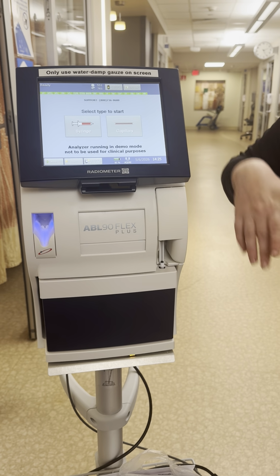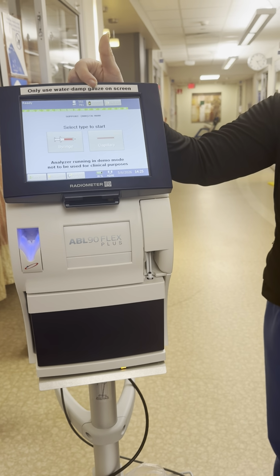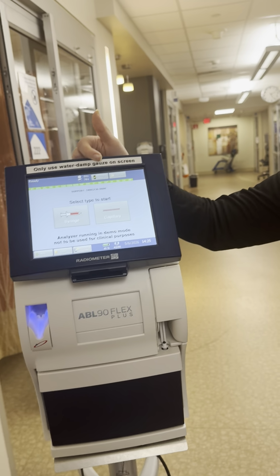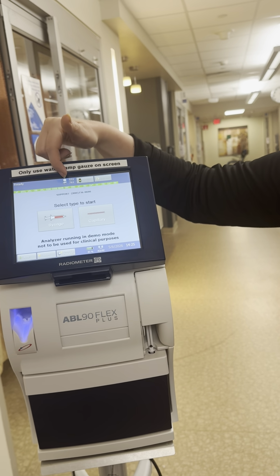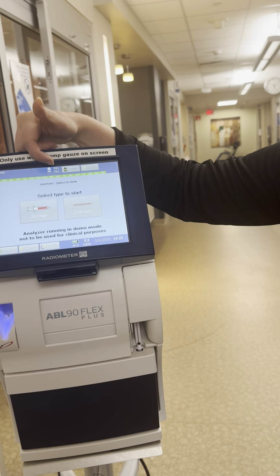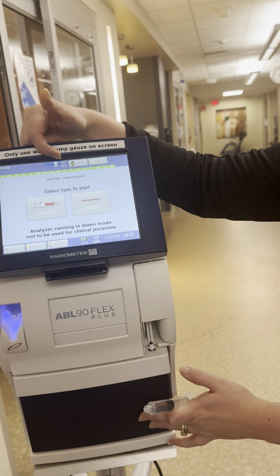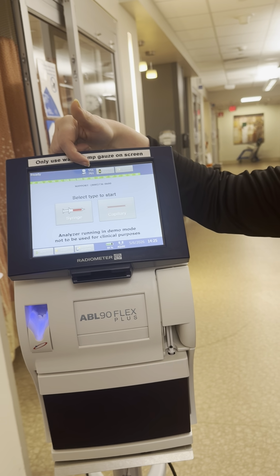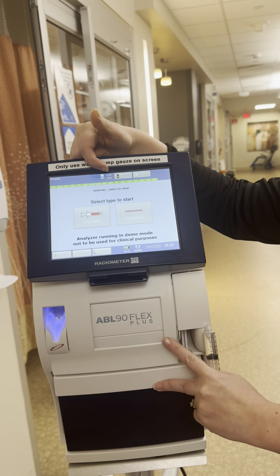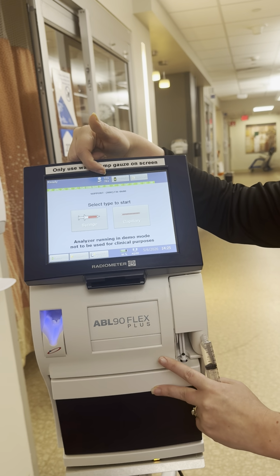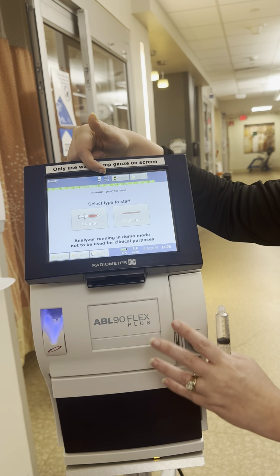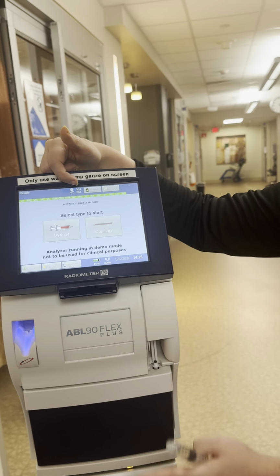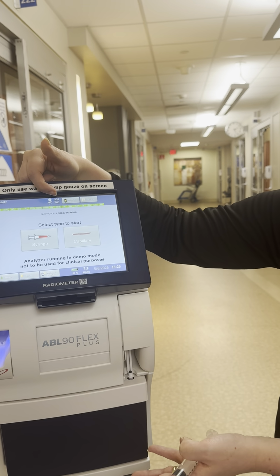So on your stoplight at the top, this is where you are going to see if you have to troubleshoot, replace, or fix anything. Right here beside it, there's a number beside your sensor cassette and your sample pack showing how many tests are left to run. These are going to have to be replaced every 30 days or when they run out. We are starting with the max size of both of these. They do make different sizes based on how many samples they can run. So we're starting with the max sizes. We'll see how we go through them.